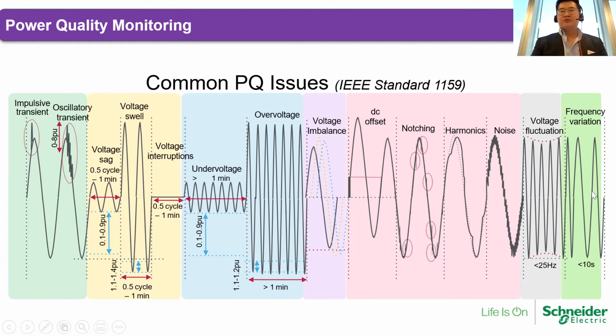Another problem is harmonics - the waveform is very irregular. Harmonics cause overheating, especially overheating of the transformer neutral - that's the major problem with harmonics. Where do harmonics come from? From data centers, especially in Hong Kong, where we're building quite a lot of data centers, particularly around the Tseung Kwan O area, and also in Kwai Chung and Sha Tin. Quite a lot of harmonics - they are pollutants, actually.